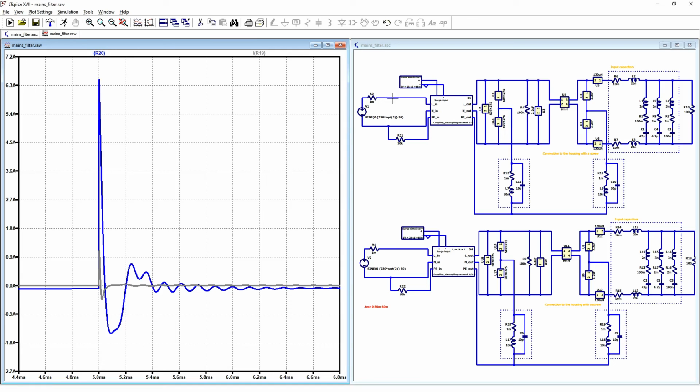Remember that a surge pulse always needs a coupling decoupling network to couple into the line through capacitors. In the next video, I will focus on electrical fast transient, the so-called burst. It's similar to surge, but with less energy.